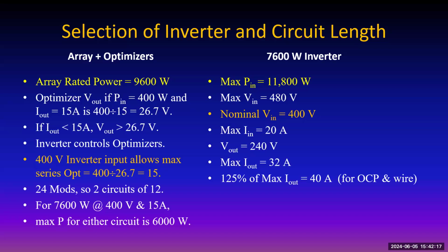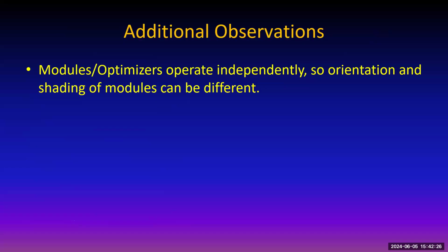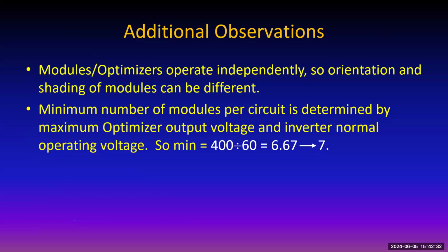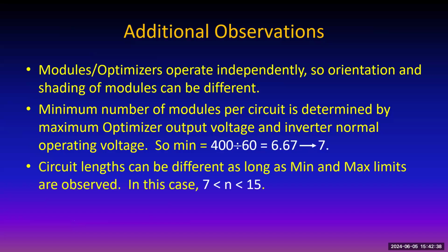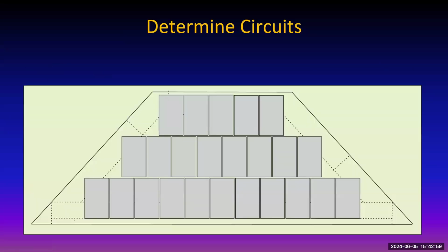So from all these things, you can determine the length of the string, the maximum and the minimum number of modules. So the nice thing is the modules can be different and be oriented in different ways. The minimum string length is 7. The maximum string length is 15, so you can have anywhere between 7 and 15 in a string for however many strings that you have. And they're still all going to operate at maximum power as long as the strings are in length between somewhere between 7 and 15. Okay, so how would we do that?